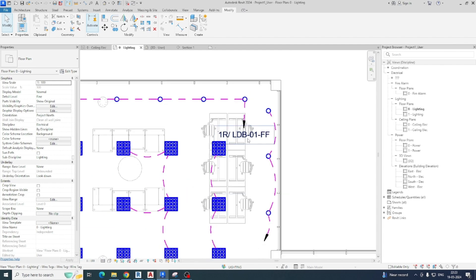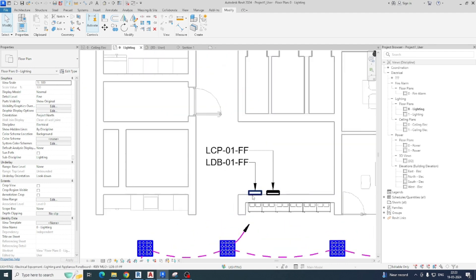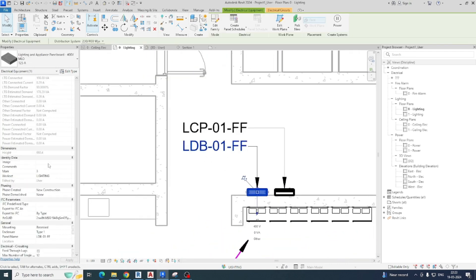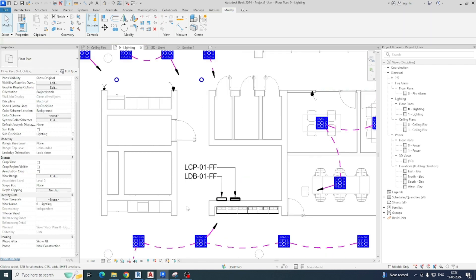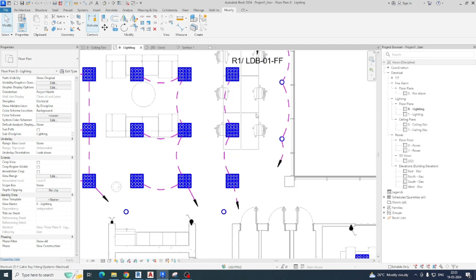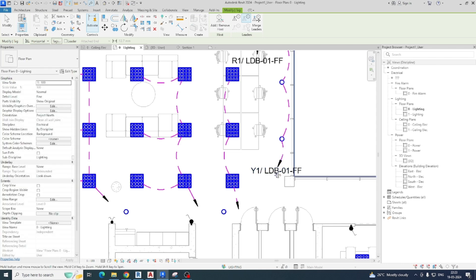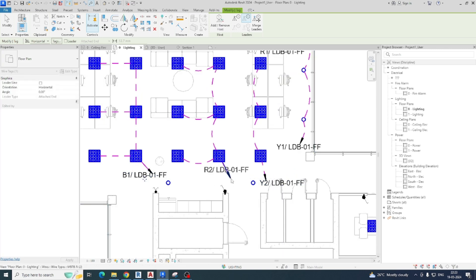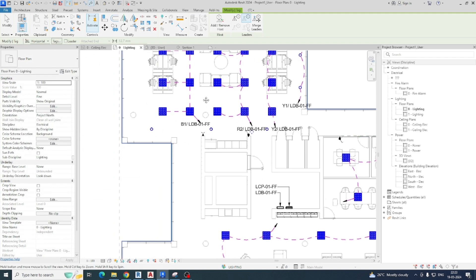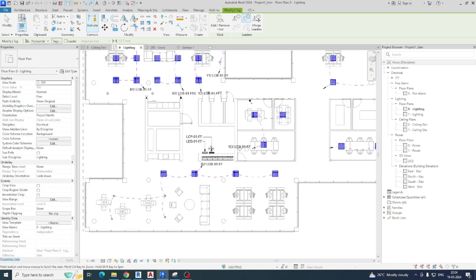To get R1, select the panel first, go down and you can see Circuit Naming — select it by phase. What will happen is it will automatically change to R1. If you give a tag it will show Y1, this one Y2, another one B1, this one R2 — automatically creating the sequence: B2, R3, Y4.